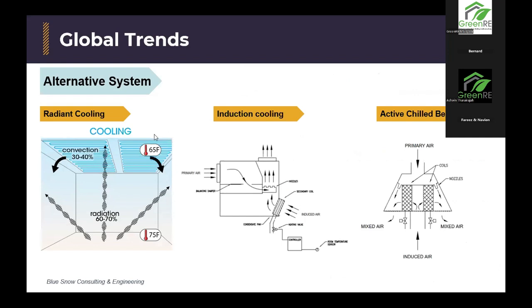Other than that, earlier what Faris showed was the FCU and AHU. That is what is known as the common systems for cooling the space. Then we have what is known as radiant cooling, which is cooling the space via radiation. But there's a caveat to radiant cooling. It only handles sensible load. You cannot handle latent load because, like I said, to remove latent load is removing moisture, meaning you literally condense the thing out. That's why you see FCUs and AHUs, they have a drain pan that collects condensate water and then just throws it out somewhere. Whereas this one doesn't do that. So you need to know how to decouple your load and use a DOAS to properly design the systems.